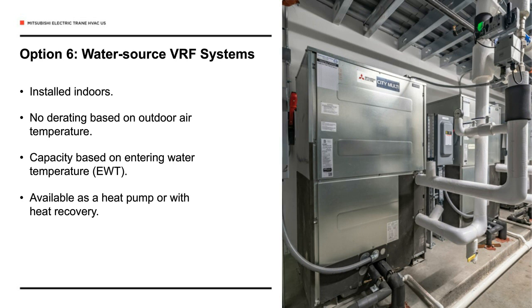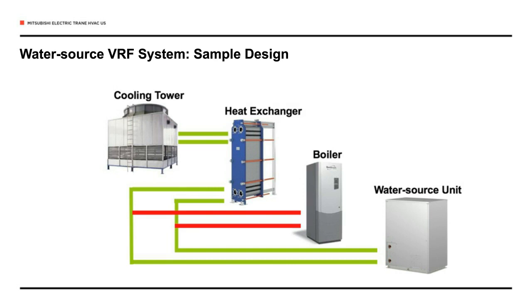And you can get water source VRF systems just like the air source in either a heat pump changeover system or a heat recovery system. Just a schematic showing that. One thing to keep in mind with water source systems, it has to be a closed loop system. So we show a cooling tower there with plate and frame heat exchanger. You never would want to just run cooling tower water through the water source condensing unit. It would get fouled up fairly quickly and derate in performance very quickly. So you either want a cooling tower heat exchanger combination or a closed circuit fluid cooler. And then, like I mentioned earlier, the boiler to temper the loop as it drops below the predetermined temperature of usually around 60 degrees.